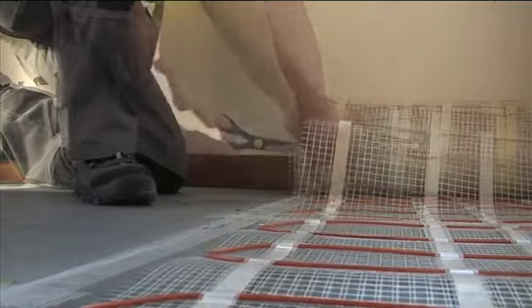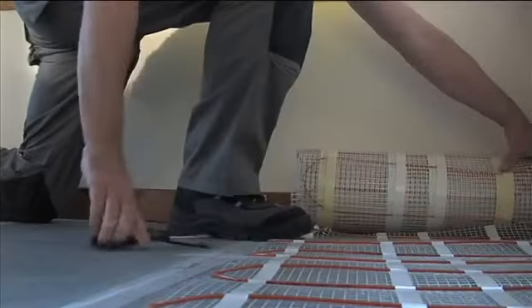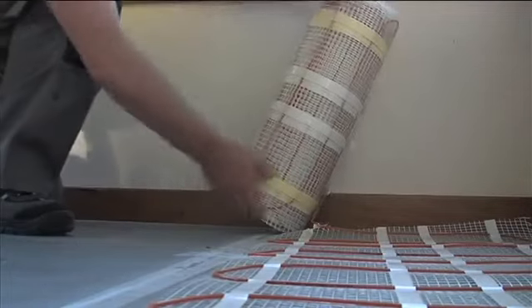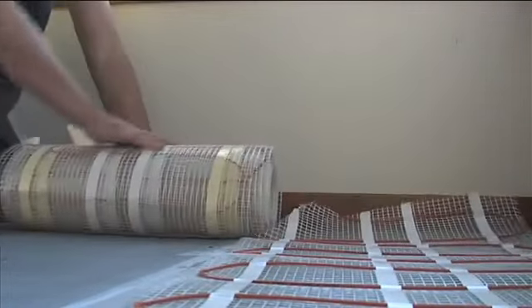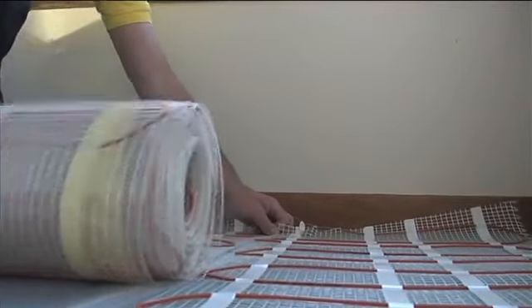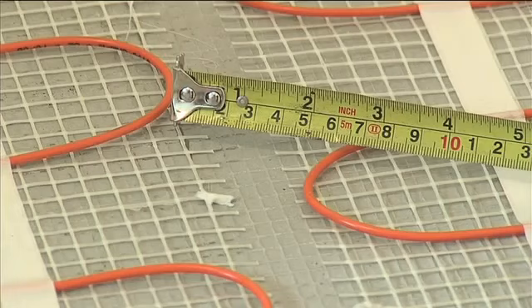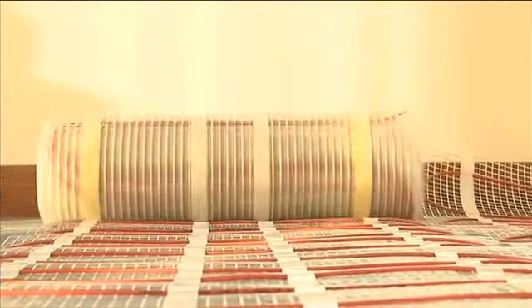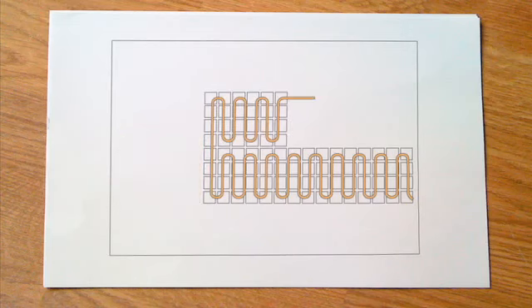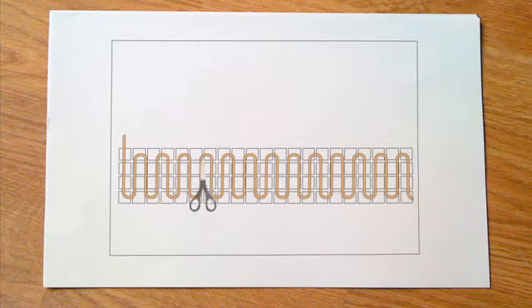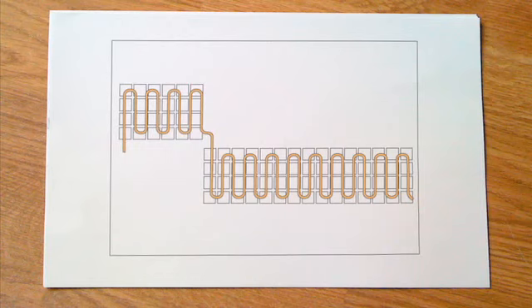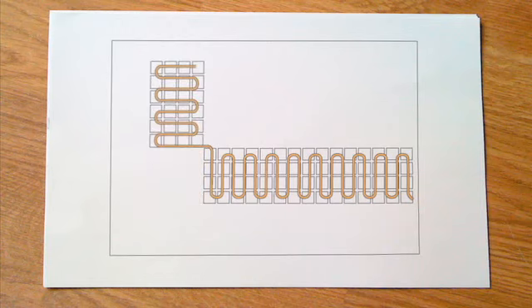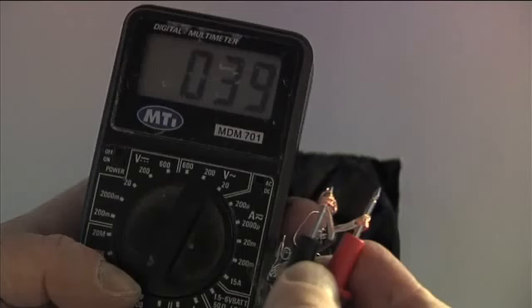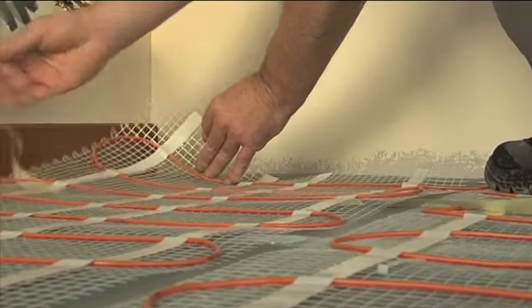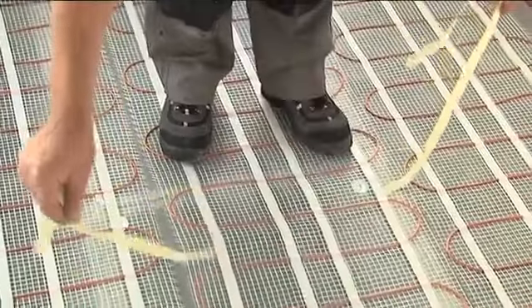When you reach the end of a run, simply cut the backing mat and turn through 180 degrees. Care should be taken not to cut through the orange heating cable. The mat is unrolled in the opposite direction, ensuring a minimum spacing of 50 mm between the cable loops. When satisfied with the mat layout, recheck the cable resistance. Stick the matting to the floor using the integral adhesive fixing strips.